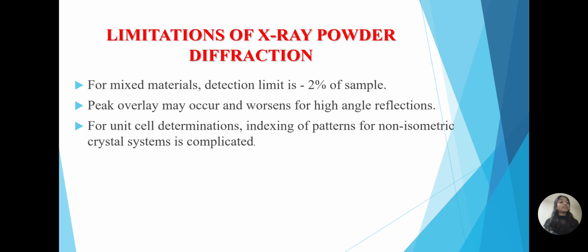Next, there are the limitations. The limitations of X-ray powder diffraction are: for mixed materials, the detection limit is 2% of the sample. Peak overlap may occur and worsen for high-angle reflections. When we see high-angle reflections, peak overlap will occur. This is a disadvantage of X-ray powder diffraction.